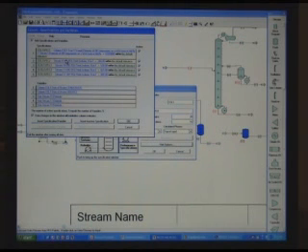And you could, let's see, stream flow rates, stream column, liquid flow rate. Yeah, this is overflash. Usually people put an overflash spec of how much liquid should be coming down out of the heater section, and then they'll vary the duty of the furnace, the heater here in this case.